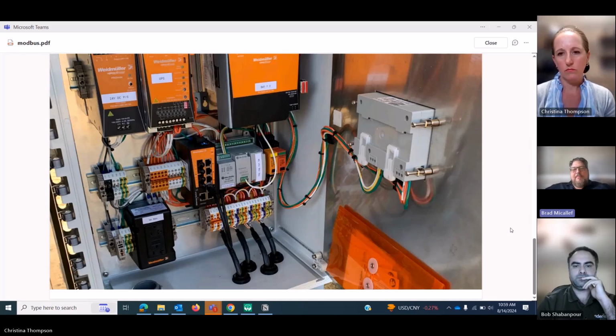It looks like they are maybe white and yellow coming into the top of that PLC that are connected to all the sensors below. So Wiretap allows us a really surgical methodology for being able to come and either do whole plant-wide communication discovery of devices and registers, or we can do something very surgical where we can just look at a particular part of the plant that is communicating on serial chains, which are notoriously difficult to reverse engineer and find information on.